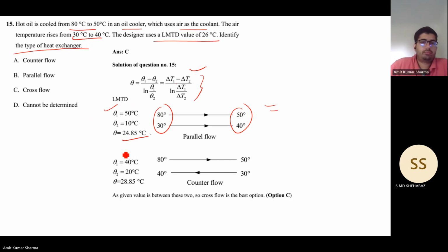For the counter flow, it's 80, 40 and 50, 30. So it comes to be 28.85. It is having more temperature difference, so it's going to be the best one. So the best is cross flow heat exchanger.